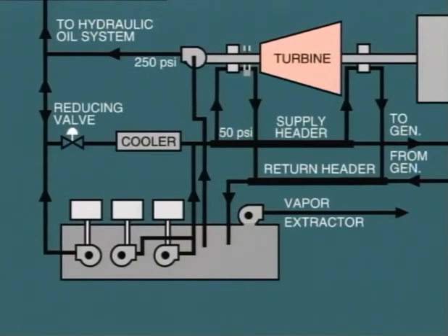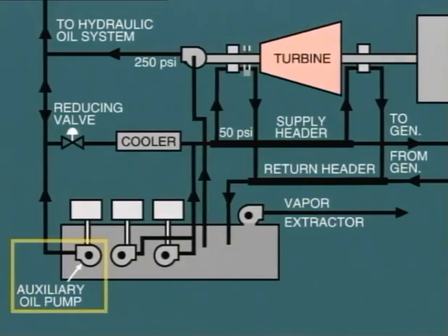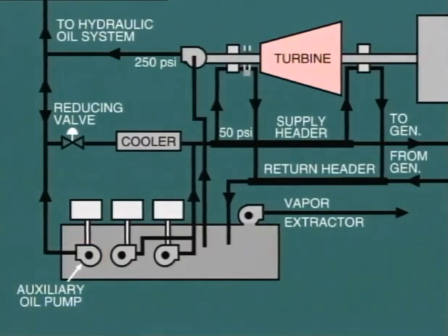During start-up and shutdown, a motor-driven high-pressure oil pump is used. This supplies both the hydraulic oil system and the lube oil system. In this arrangement, this pump is known as the auxiliary oil pump since it is the main standby to the shaft-driven pump.